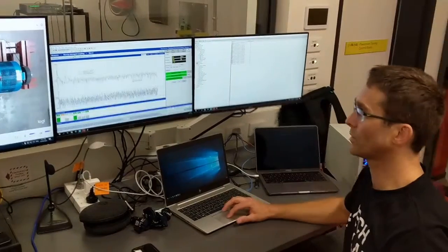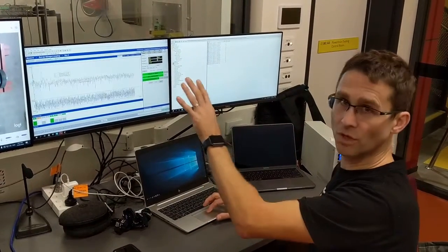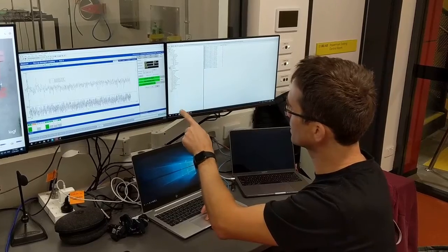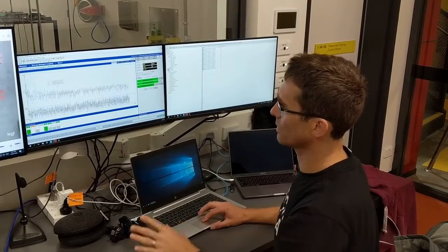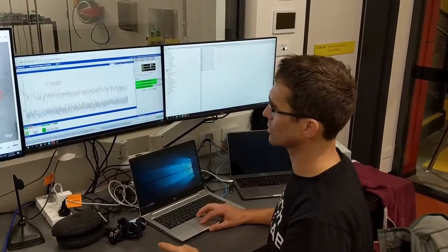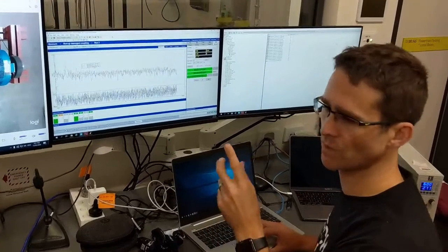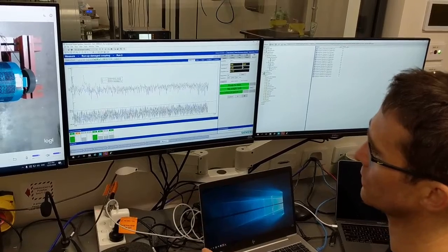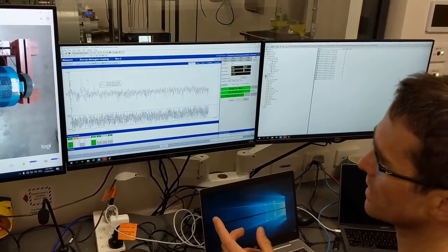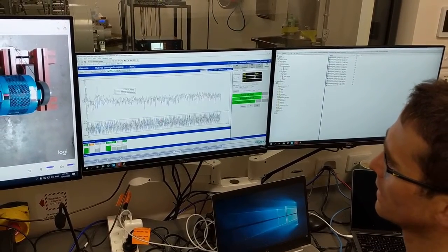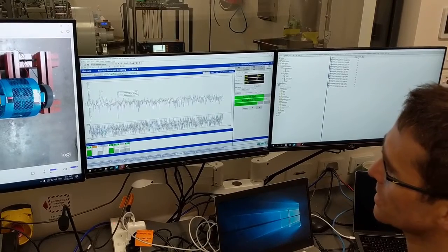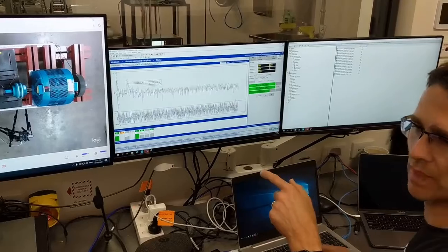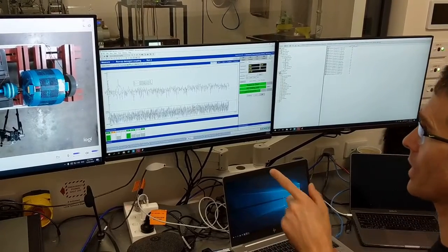On this side you can see, as I've shown previously, the acquisition system here. We're currently armed, so we're seeing live data coming through. I've created a virtual channel in here, which is the difference between the two laser vibrometer signals for the velocity, angular velocity, so we instantaneously get a delta omega. The green channel here is essentially the vibration across the coupling that we've shown. We've deliberately damaged the coupling in this scenario here.